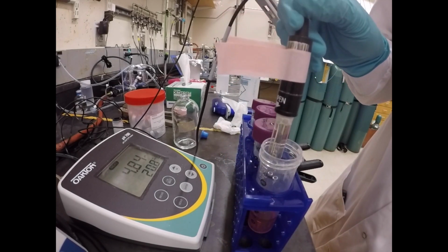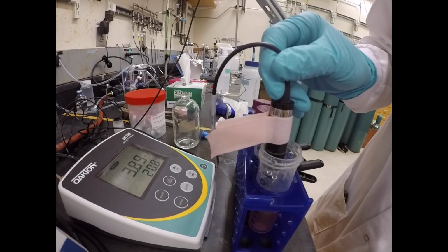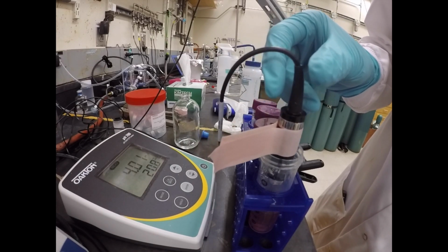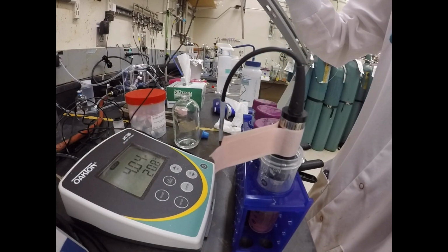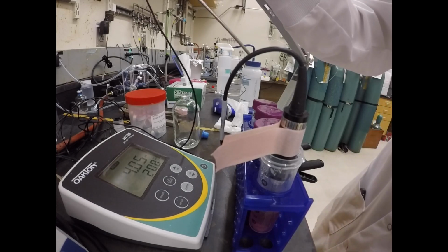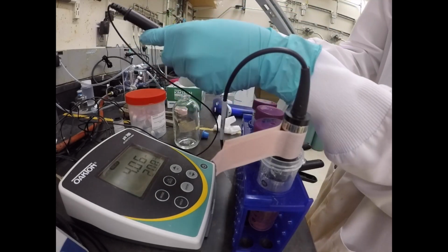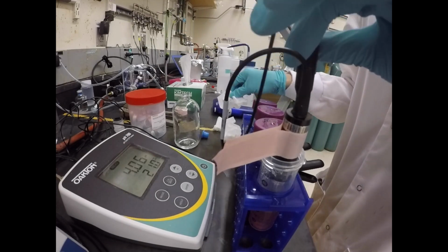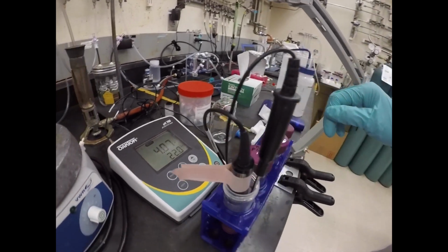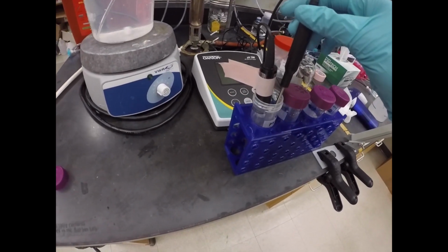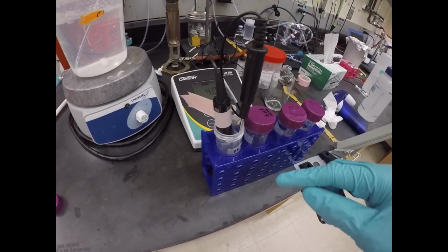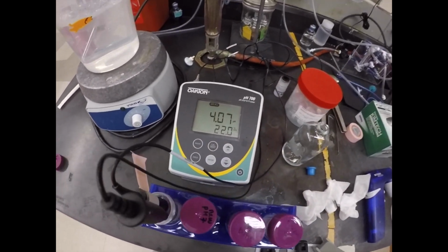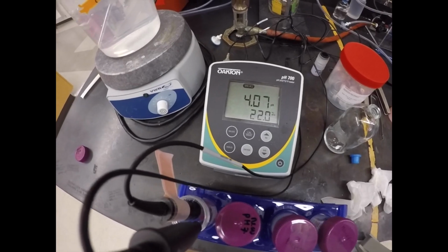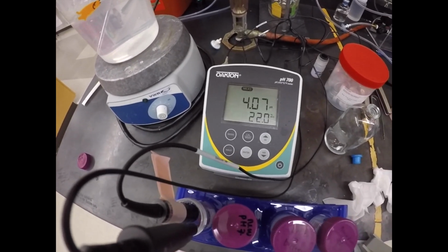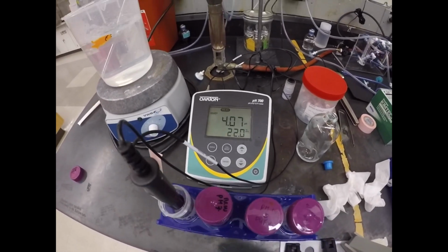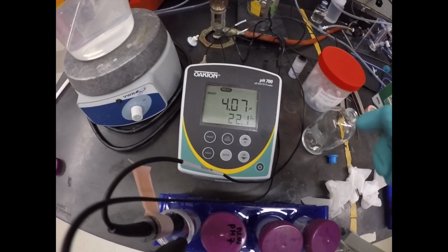So just gently place it in the falcon tube. And same for the temperature probe. So now you have both the pH probe and the temperature probe in the standard solution. And the pH reading is 4.07, which is not too bad because this is supposed to be pH 4.